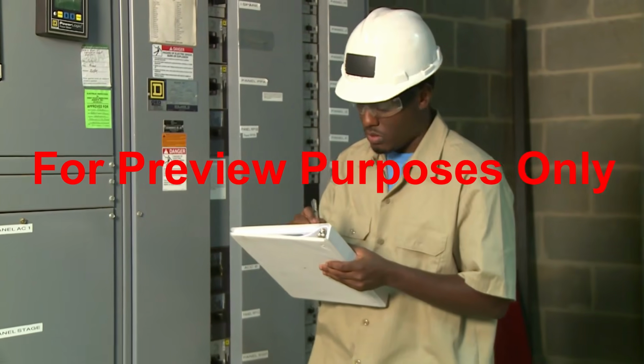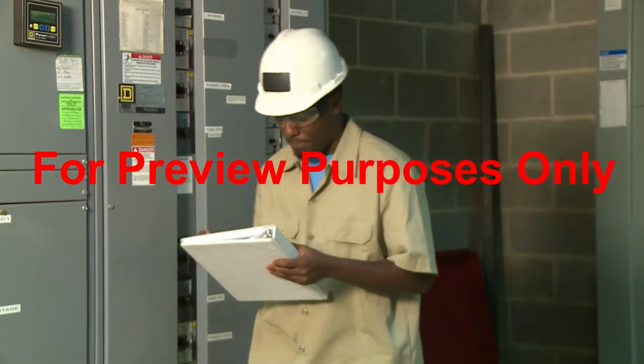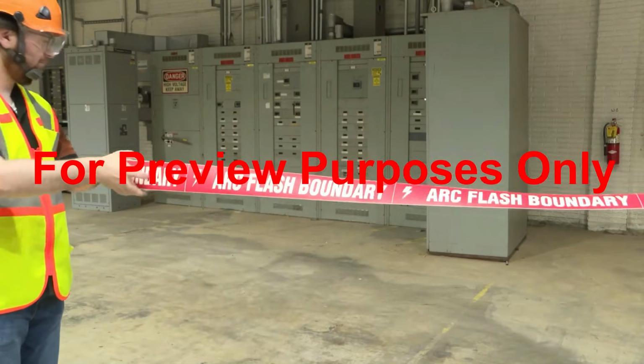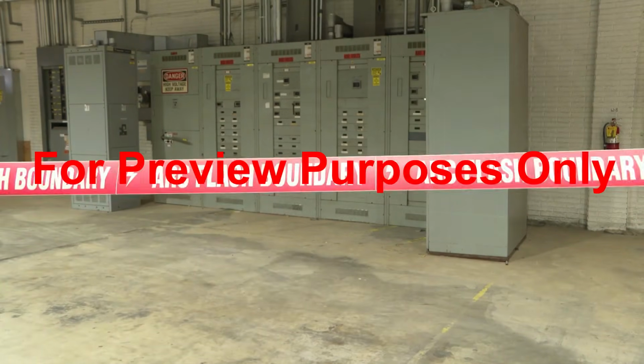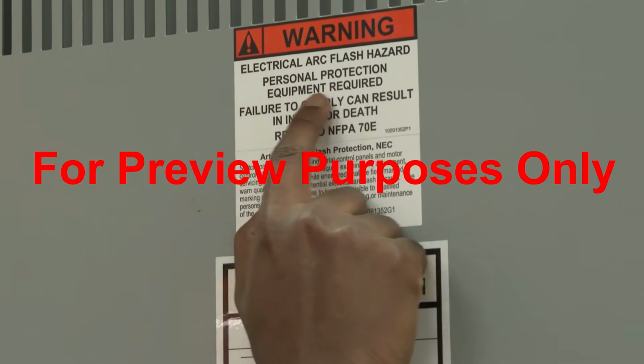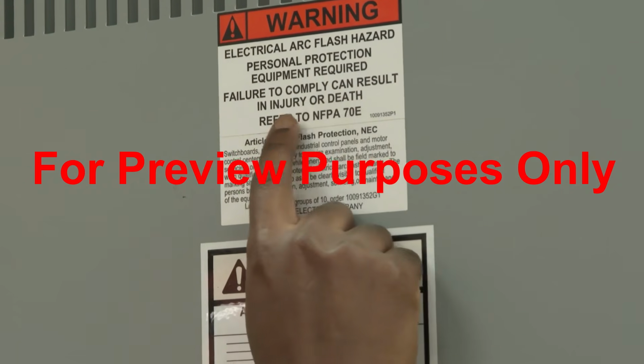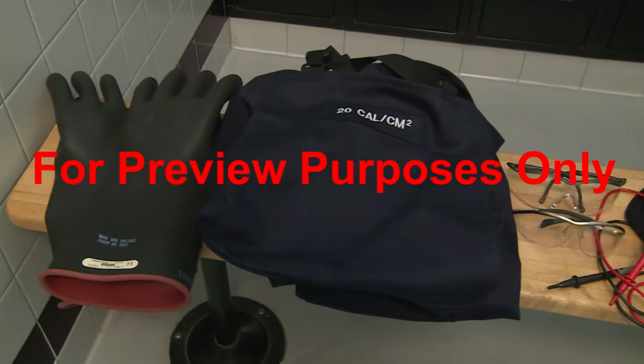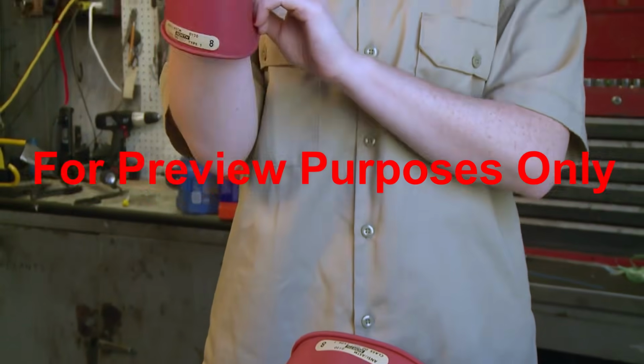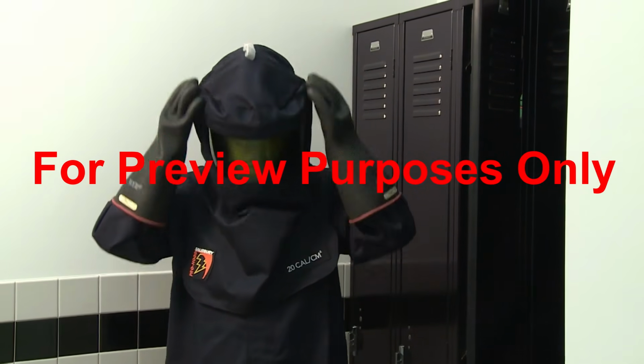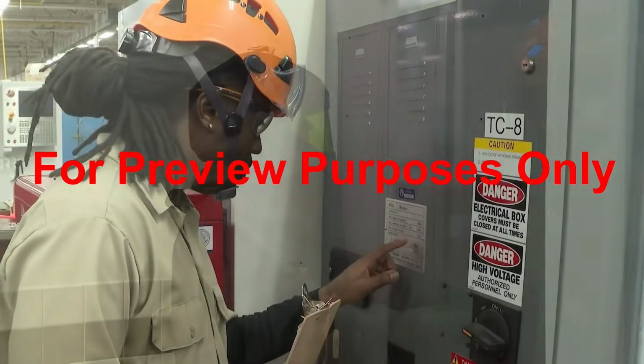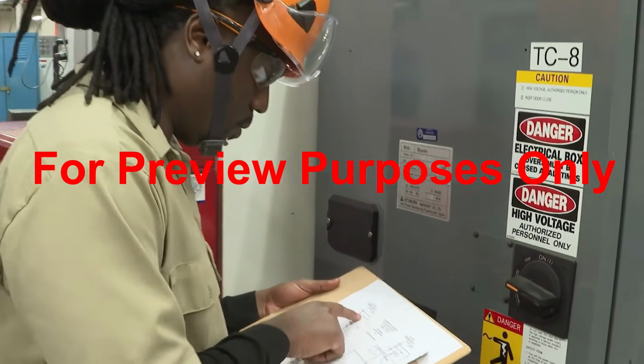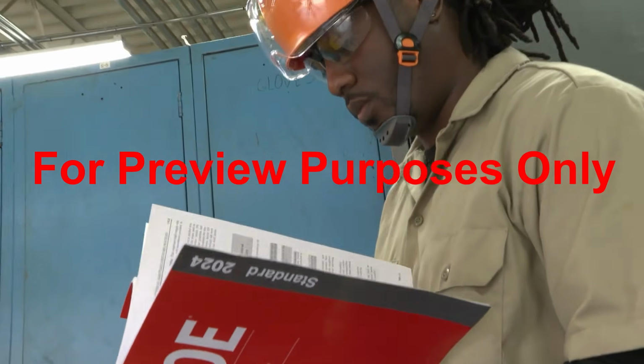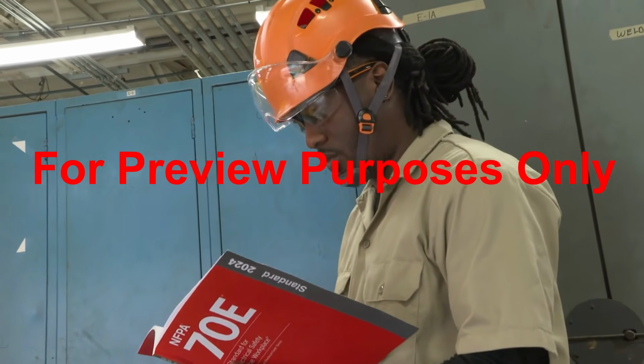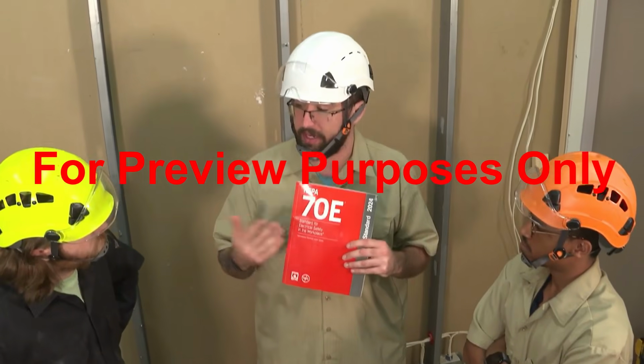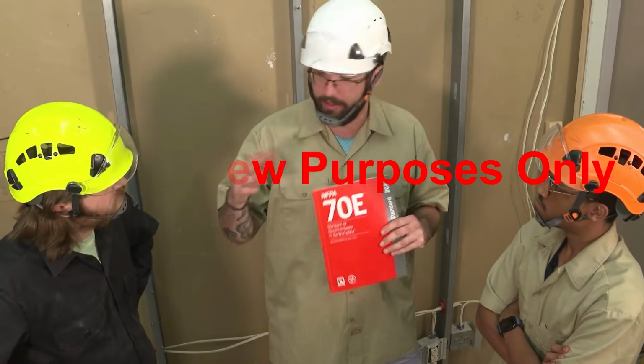Before beginning any electrical work, you should always establish the electric shock safety boundary and the arc flash boundary for the equipment you're working on. One way you can become familiar with the electrical equipment on your job site is by thoroughly reading their labels. You should wear PPE such as insulated gloves, leather footwear, and head and face protection when you're doing electrical work. Now that you know what type of electrical hazards you may encounter and how complying with the NFPA 70E standard can help you protect yourself from them, you can keep yourself, your coworkers, and your job site safer every day.